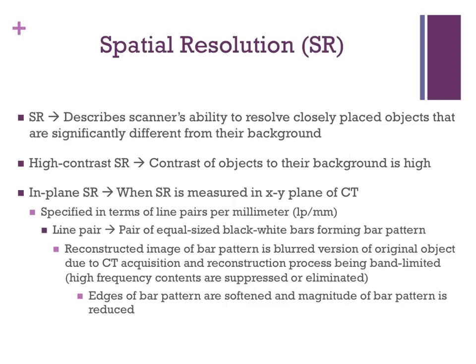In-plane spatial resolution is when spatial resolution is measured in the XY plane of CT. The in-plane resolution is specified in terms of line pairs per centimeter or line pairs per millimeter. A line pair is a pair of equal size black and white bars forming a bar pattern.